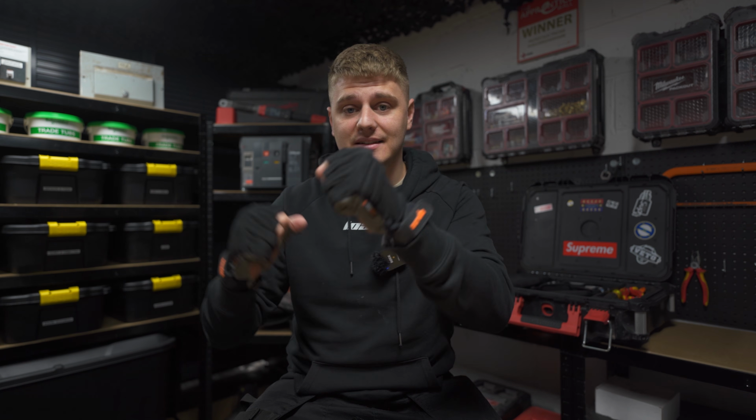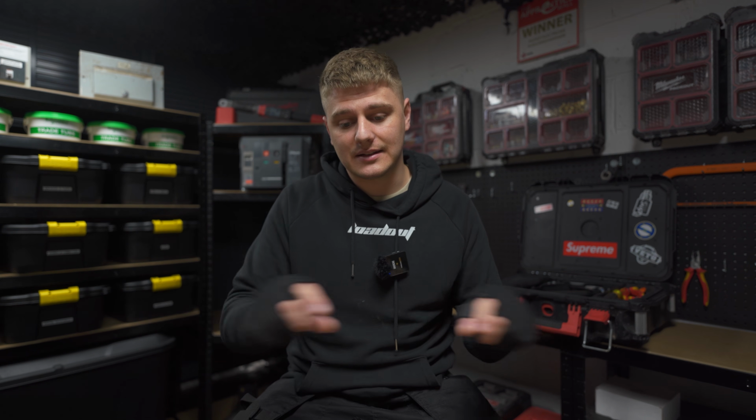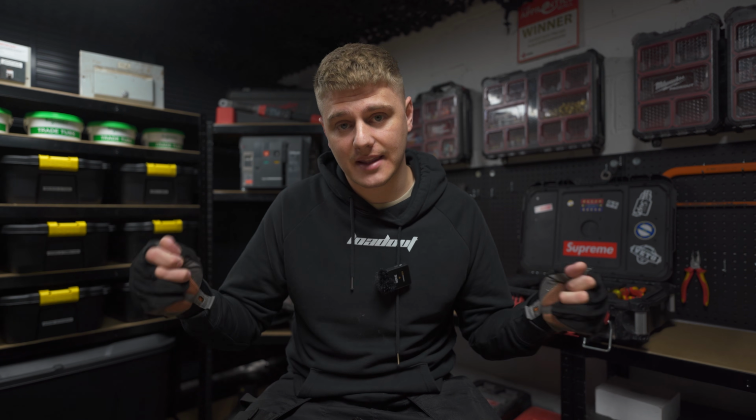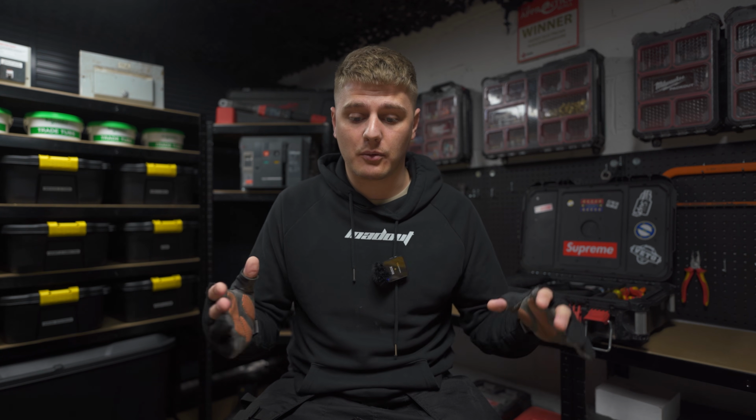They might try to catch you out there, where the bonding tests out fine if you don't disconnect it. If you independently disconnect the bonding cables and test them alone, you might find that one of them is actually broken, and that is the fault. But without disconnecting them and following the process to the book, you never actually find that fault. So just something to consider there.